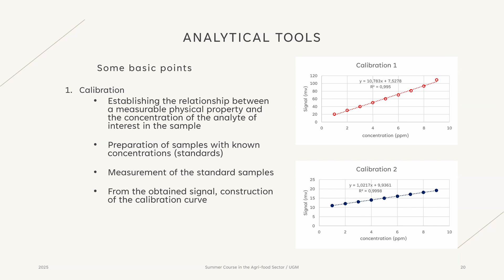Most of us can say that calibration 2 is better than calibration 1 just because the coefficient of regression is much better. It's three 9s and an 8: 0.9998 here versus 0.995. So it looks like calibration 2 is better than calibration 1. However, let me take you to a different point.